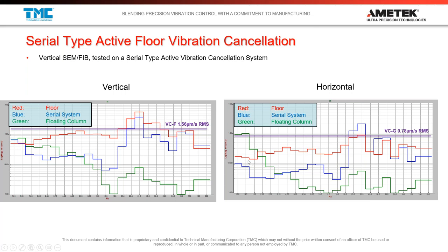We see the same story horizontally here, where you've got some green, red curve here, which is the floor. Here's the horizontal, and resonance of the tool's own internal isolators. And then again, very good reduction of the floor vibration using the serial type system.